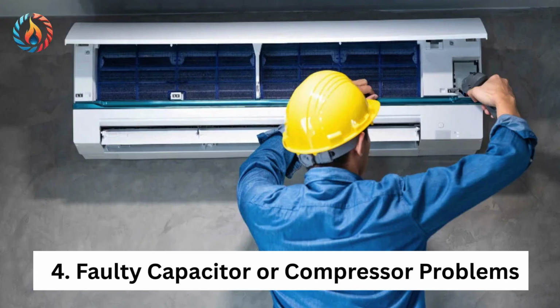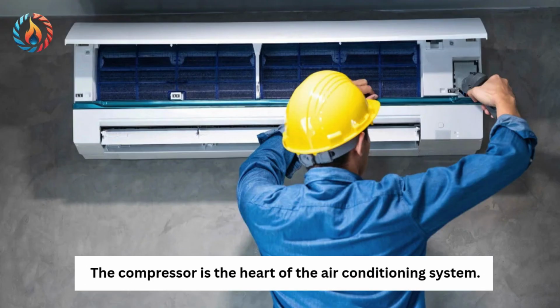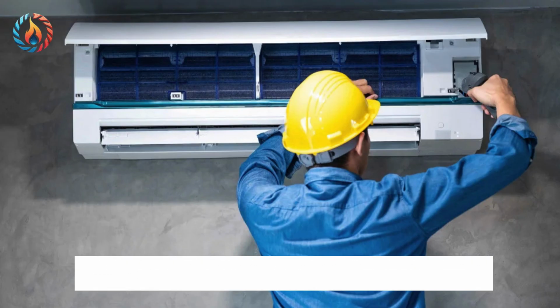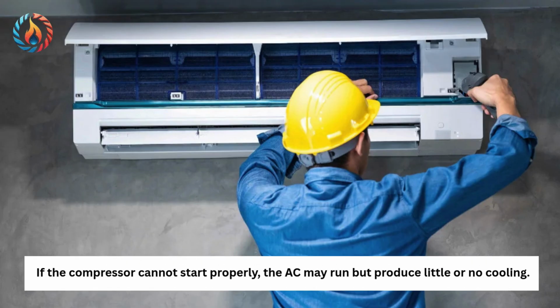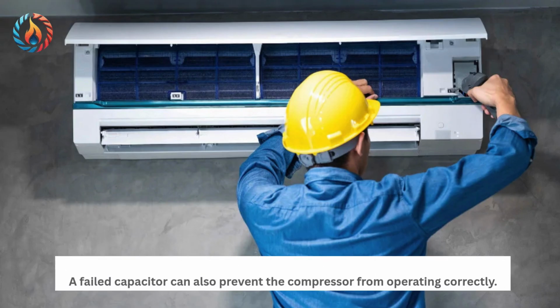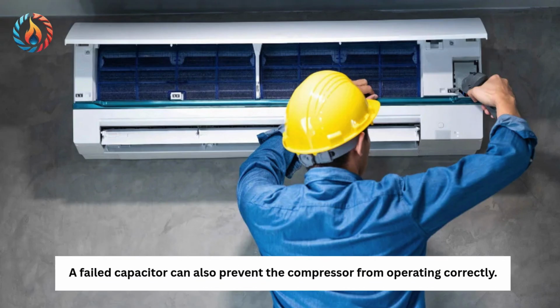4. Faulty capacitor or compressor problems. The compressor is the heart of the air conditioning system. If the compressor cannot start properly, the AC may run but produce little or no cooling. A failed capacitor can also prevent the compressor from operating correctly. Common symptoms include outdoor unit not running, humming sounds, frequent tripping, warm air from the indoor unit.